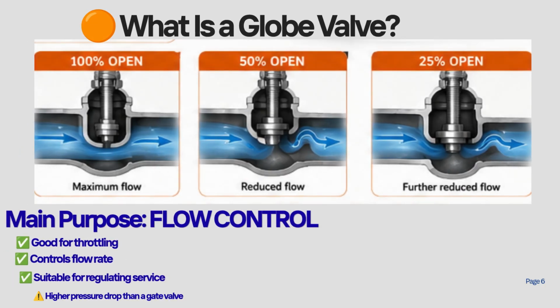A globe valve is commonly used when flow regulation or throttling is required. Its internal disc moves toward or away from the seat to control the amount of fluid passing through the valve. Because of its flow path, a globe valve generally creates more pressure drop than a fully open gate valve.